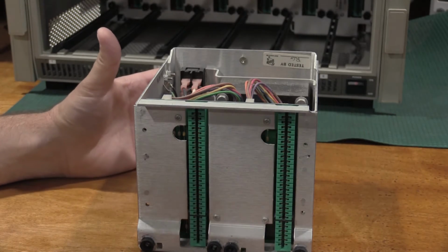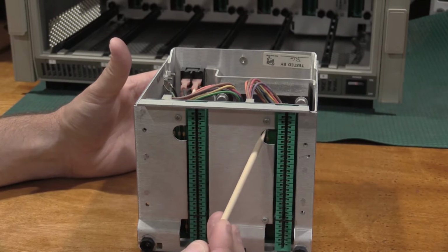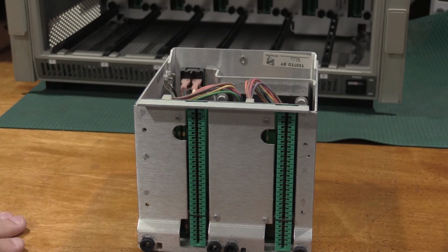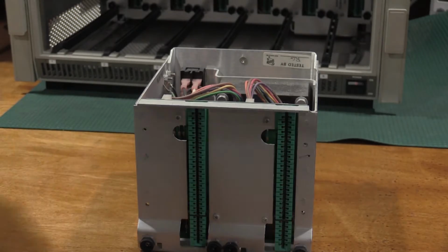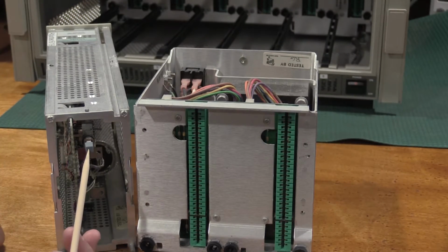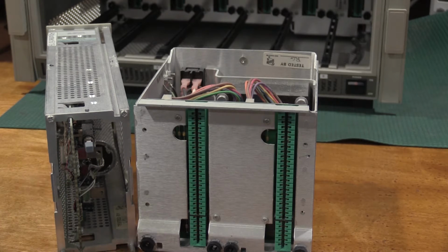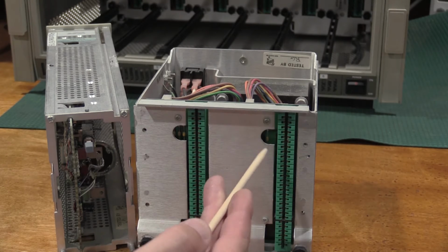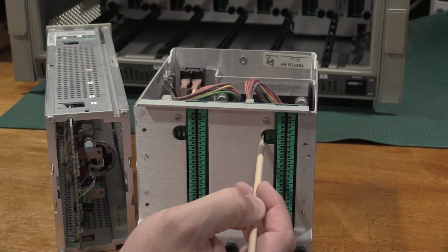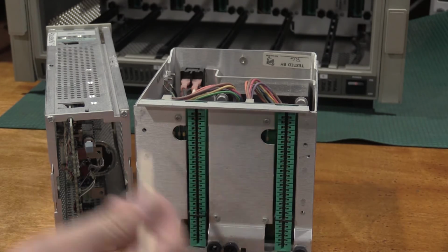If you look at the front of this module, you'll see this cutout right here. This cutout's important because on that power supply, this cutout interfaces with this push button. So when that button's not pushed, it tells the plug-in that it's a low power bay, and I believe low power means it's up to 400 milliamps or something like that. If this was solid here, this would denote it to be a high power bay, and I could get the full specification out of this power supply.